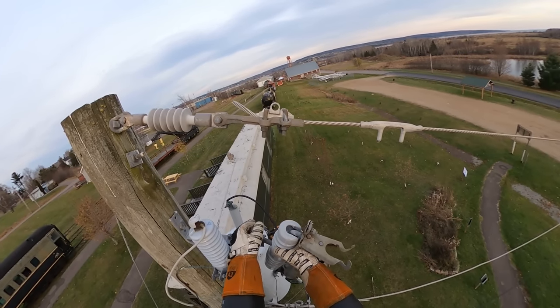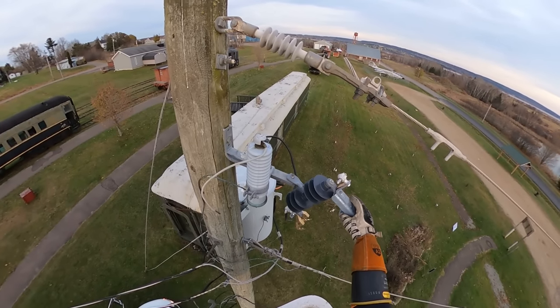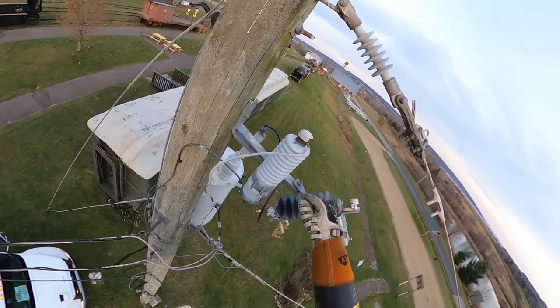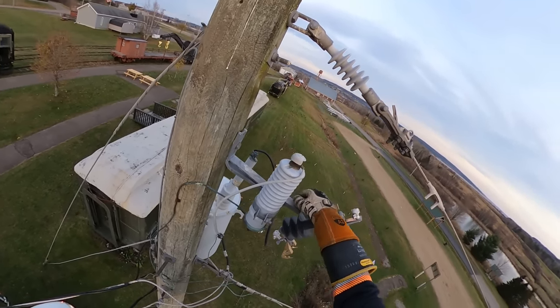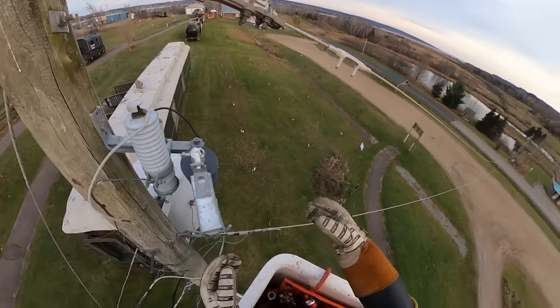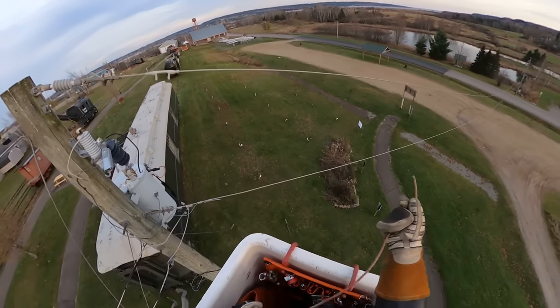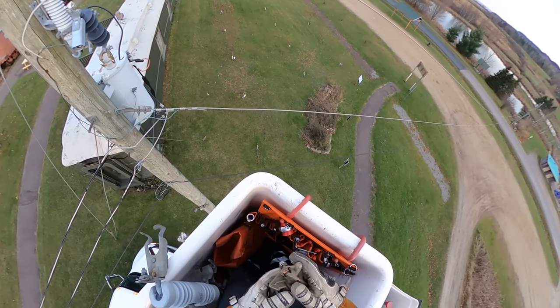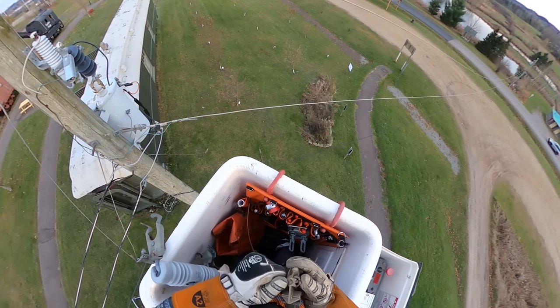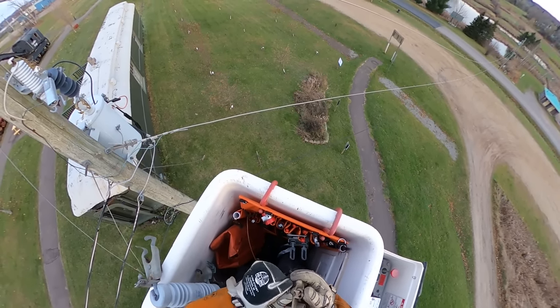Changing the cutout is pretty straightforward — we've seen it in many videos. You can see when I lifted it off, as soon as it cleared that nut I pulled it away; you're not going to aggressively lift it up near that high voltage. When I put the new cutout on, I don't tighten it all the way because I wanted to swing the cutout towards me when I put that lightning arrester lead in, giving myself a little bit more clearance from the high voltage. A lot of times what I'll do is swing it out and away from the primary, put the tap clamp on the lead from my bucket, and then put it on the L-bracket. In this case, since we're using that same lightning arrester, we're making those main connections on the top of the cutout on the structure itself, so we have to be extremely conscientious of our positioning throughout this job.